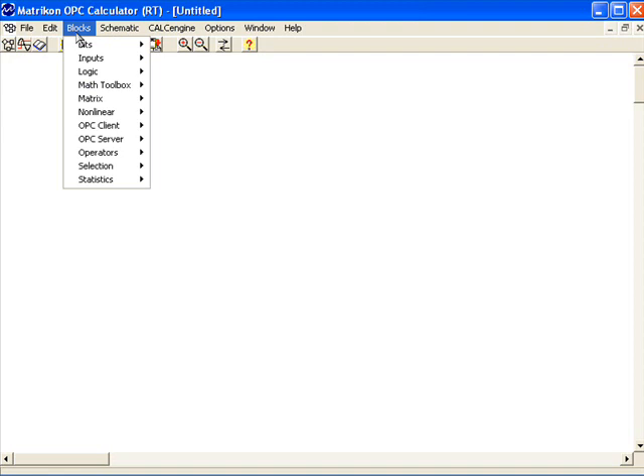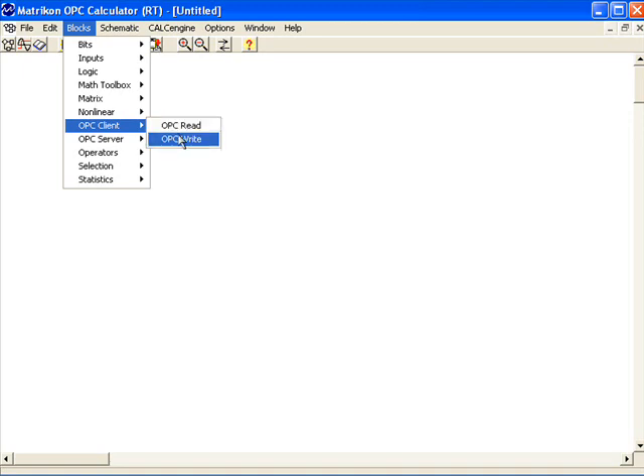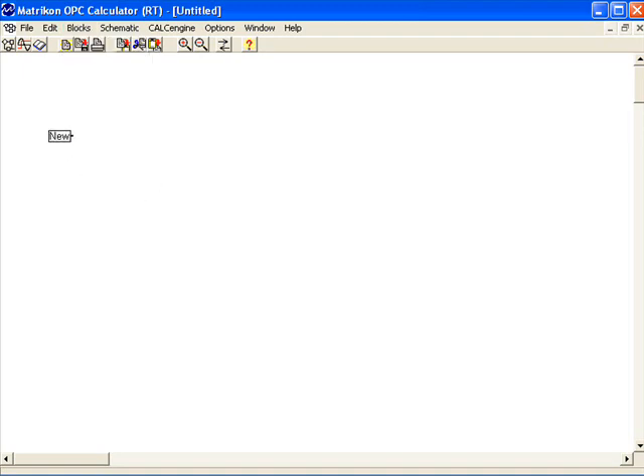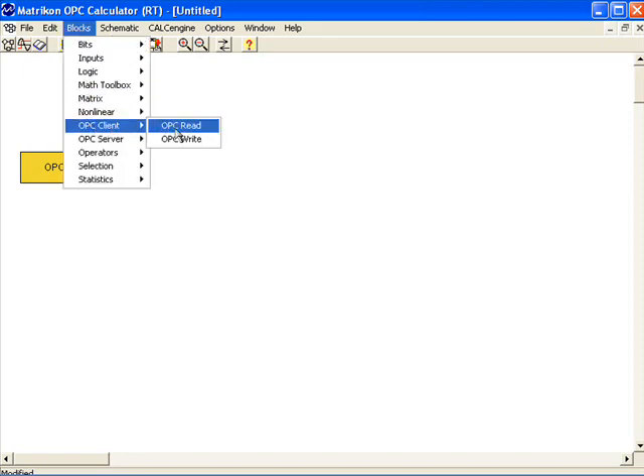All of the blocks are available under the blocks menu. For this calculation we want to connect to an external OPC server — in this case the simulation server — to bring data into the calculation. There are two types of OPC client blocks: a read block where we connect to an external data source and use it as a source for a calculation, and an OPC write block where we write the result of a calculation into some external OPC server. For this example we're going to use an OPC read block and drop it onto the schematic. Because I want to connect to two separate individual tags in the simulation server, I need two individual client read blocks.